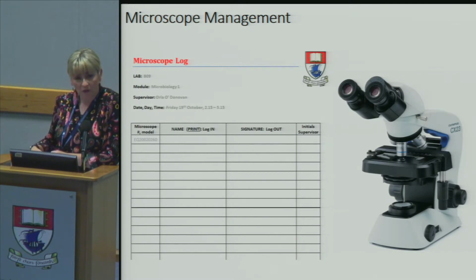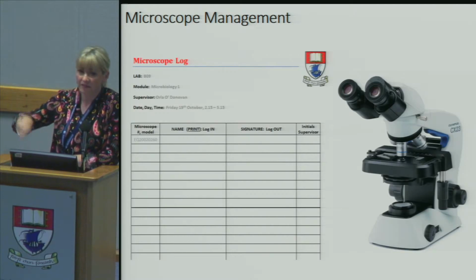But what we are looking for here is proper storage of the flex. Do not wrap that flex around the base of the new microscopes. If it cracks, you've got a potential electrical hazard happening. Don't allow excessive oil to hang around on the lenses. Clean those lenses down, because if that oil seeps up into the oil immersion lens, it will ruin it, and that will make microscopes few and far between for us because they have to be removed to be repaired. And stains. We now know stains are dangerous. So if there's stain on that microscope, clean it away using the cleaning solution so that you're not exposing other people to hazardous stains. Okay.